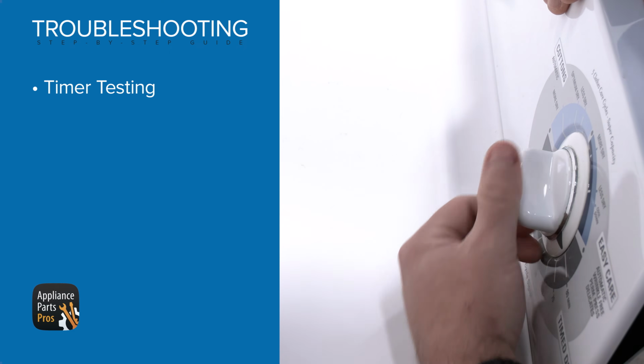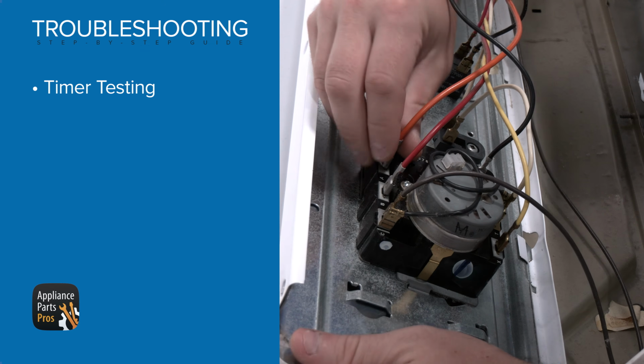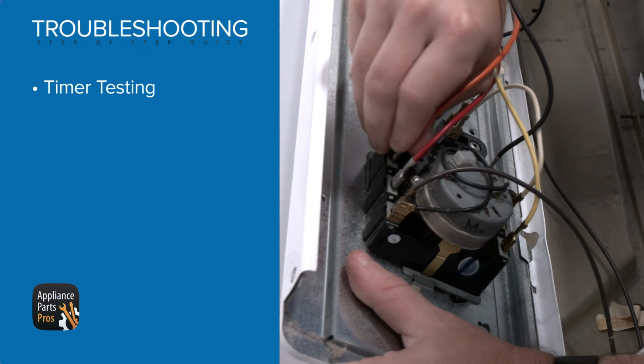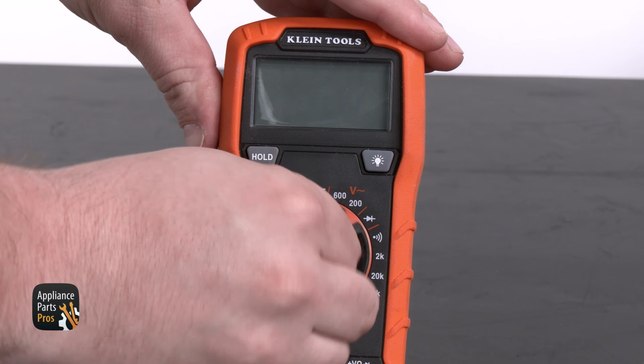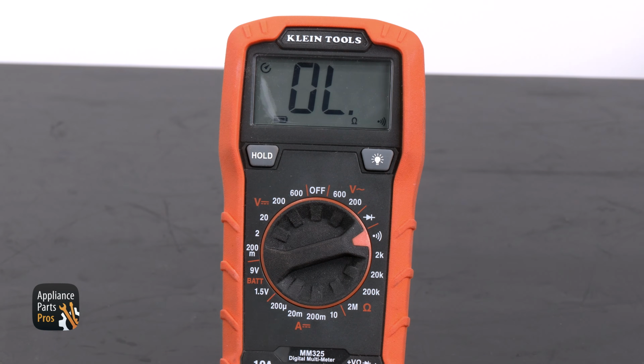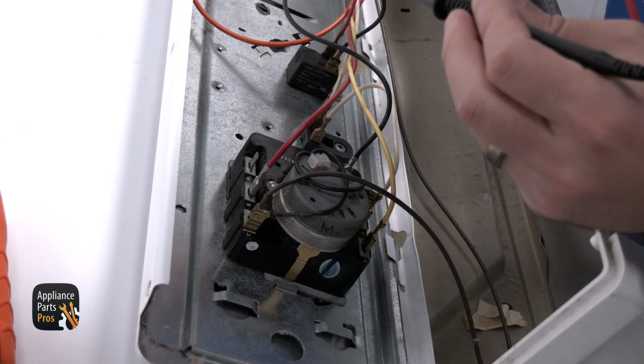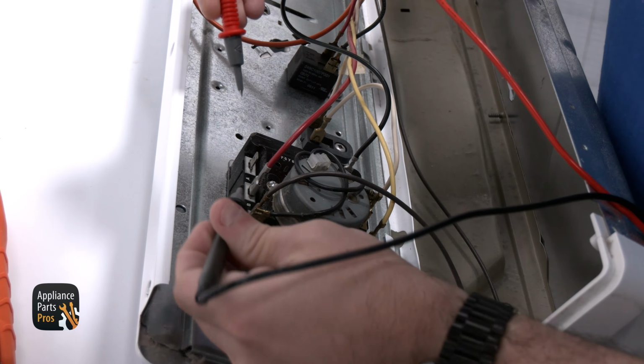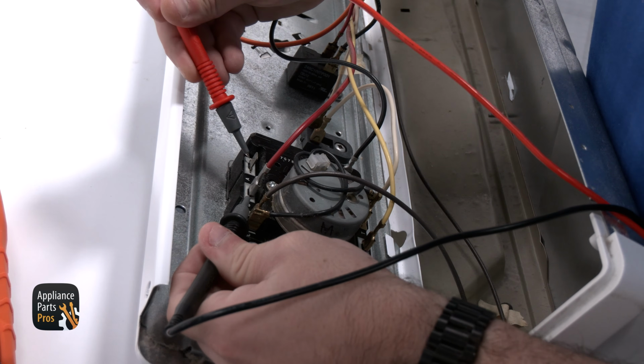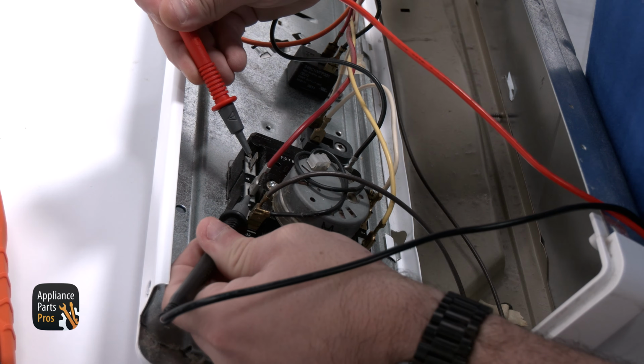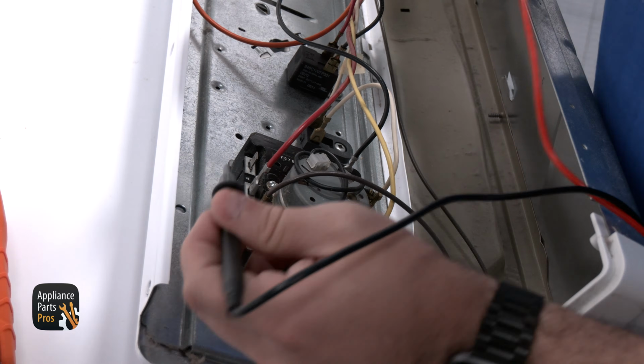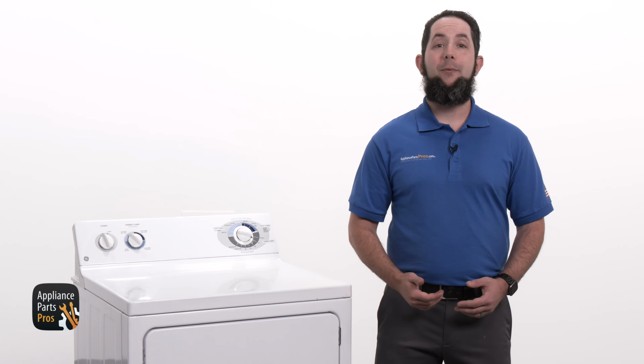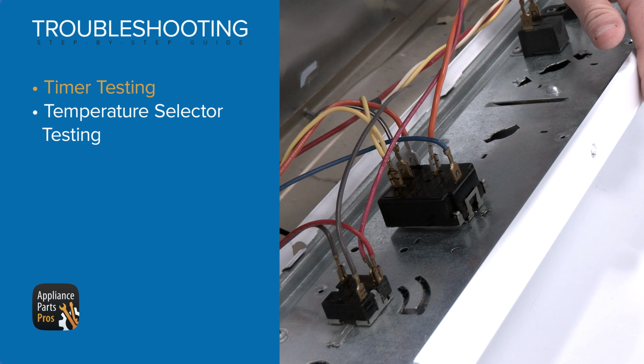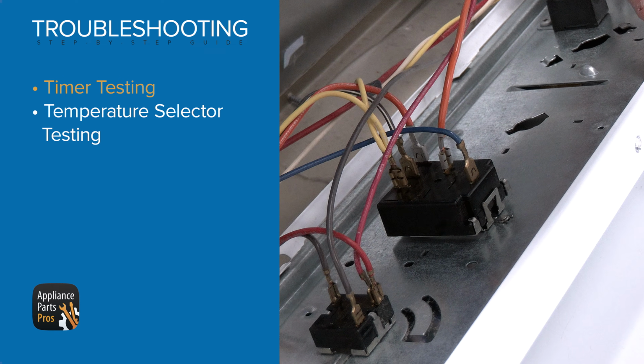Once we've accessed the timer, we're going to set the timer to a time cycle and remove the orange wire. Let's grab our meter again and set it to continuity, which looks like a sideways Wi-Fi symbol, and test the timer from terminal B to terminal A. If there's no continuity here, then the timer is going to have to be replaced. If you do get continuity, like we are here, then that means your timer is good and we'll need to continue troubleshooting.